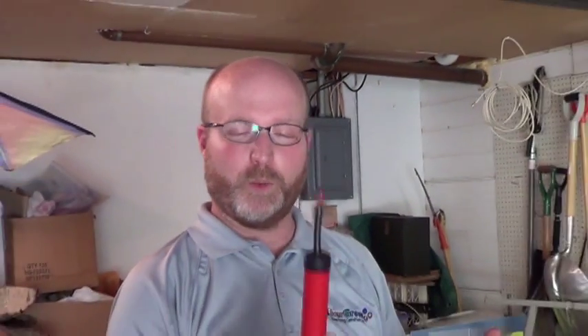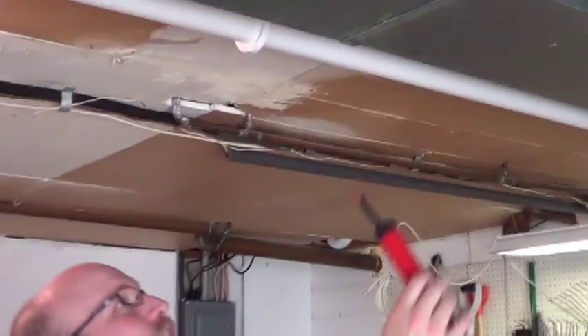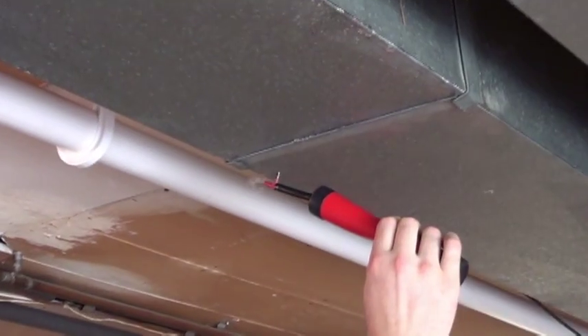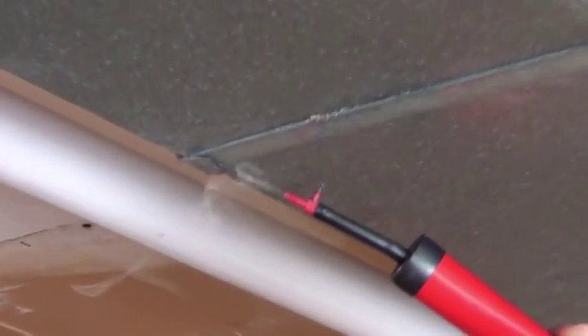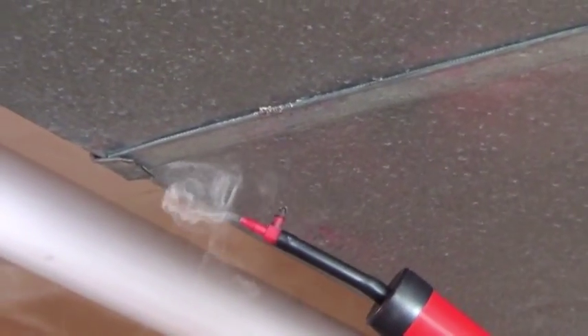So to demonstrate that we actually have duct leakage, this is one of the tools we use. It's just called a smoker, and when you squeeze it, it puffs out a little bit of smoke. And once the smoke is going out, you can see which direction it's going to show the leakage. So this is a supply duct, so if I see the air hitting the smoke and changing its direction, I know that we definitely have some leakage here that we need to seal up. Now on the return side, I would expect the smoke to go in the ducts as opposed to away from the ducts.